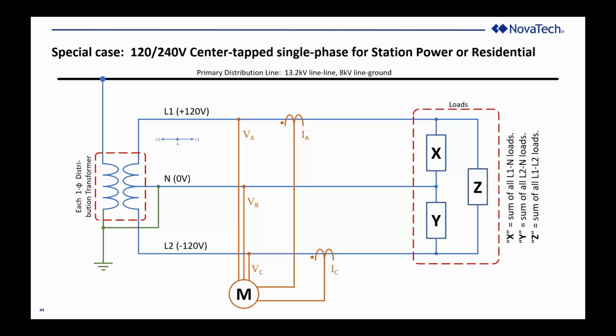Remember, as long as I don't have a fourth conductor, I can have 3 conductors. It doesn't matter that the one is at the center tap, because if this were A, B, and C, if there was a phase angle between my line 1 and my line 2, it would still have that common B phase in the middle. So I don't have a fourth conductor for current to flow. I have no zero sequence imbalance. Therefore, a 2-element wattmeter will always work on station service, which is where you typically see them used.